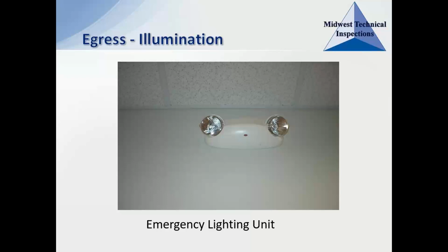And then also they have one for yes, but non-functioning. That means they're not lit up, or they're broken, or they're hanging down, they're not properly installed, something like that. Or maybe it's just a paper sign that's not illuminated. There's something that's not quite right about it. That would be the one we would mark there, and of course we would want to make a recommendation to have that fixed.